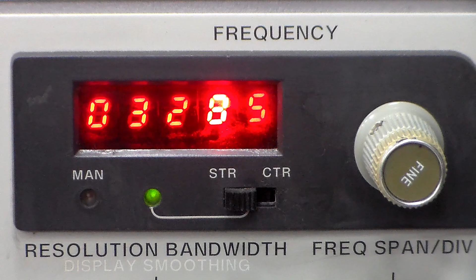Just to give a bit of an overview of the spectrum analyzer, it's a fairly traditional design where you've got the input section with attenuators, and then you come up and you've got a mixer, and from circuitry down below there's a local oscillator input into that mixer as well to give you an IF output frequency of 100 kilohertz, and then we've got the IF stage there, and then it goes through a little bit of amplification, either linear or log depending on what's selected, with a detector.